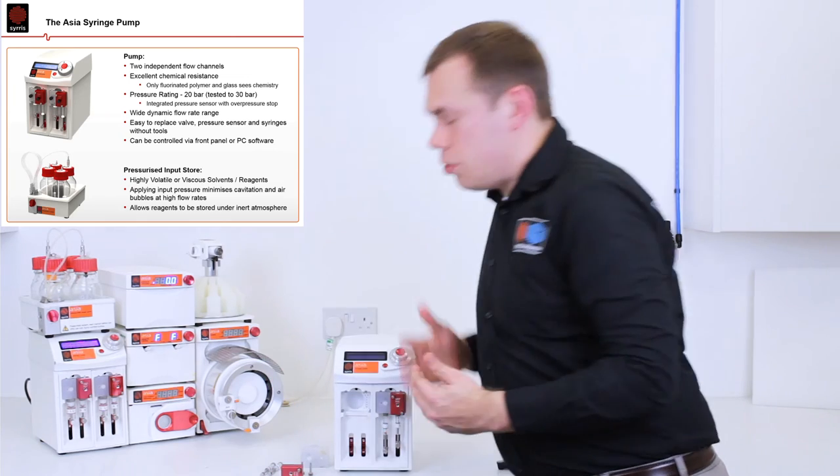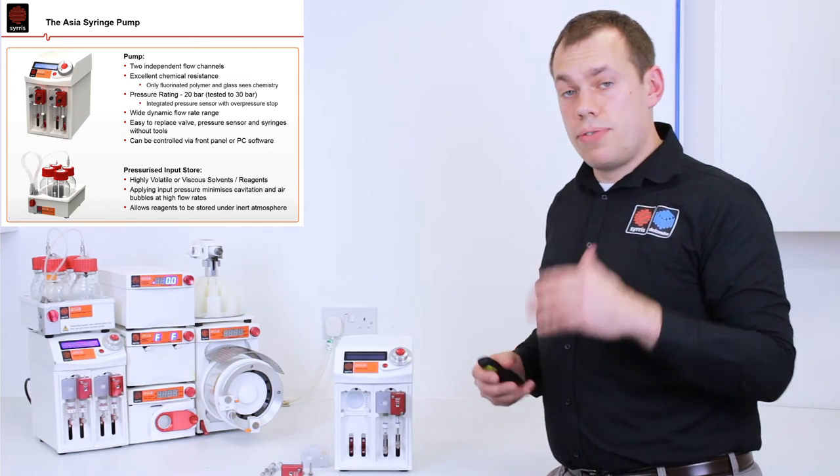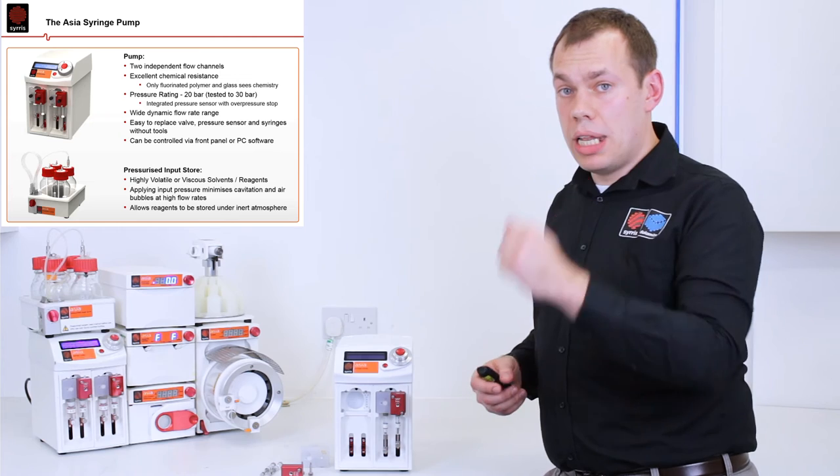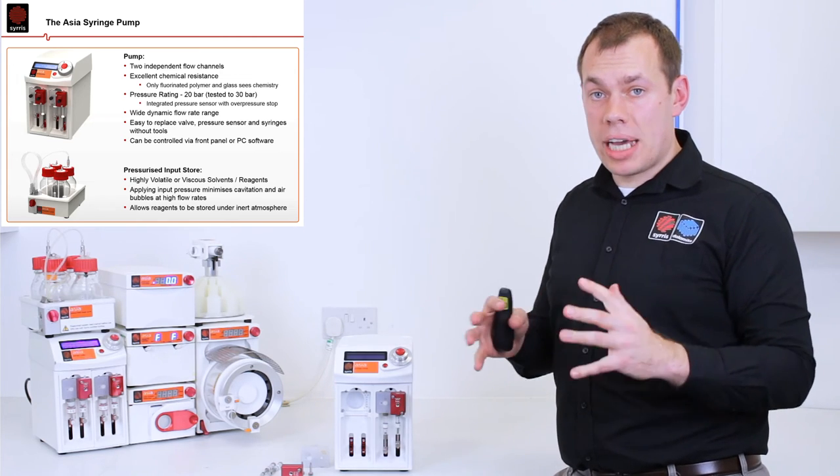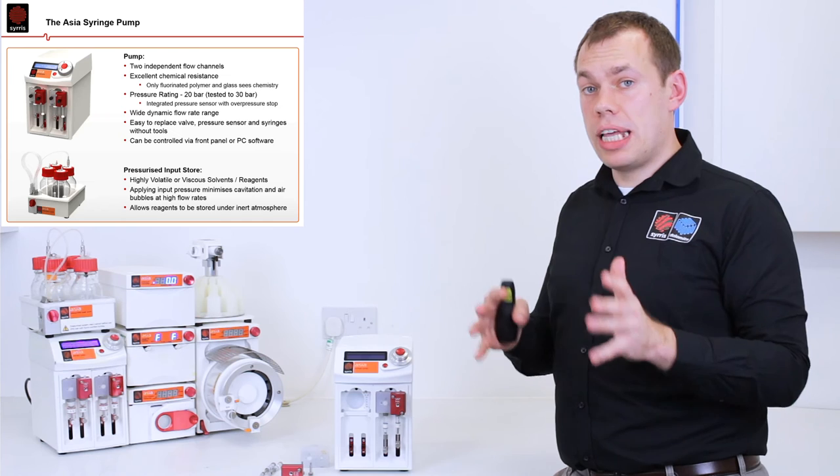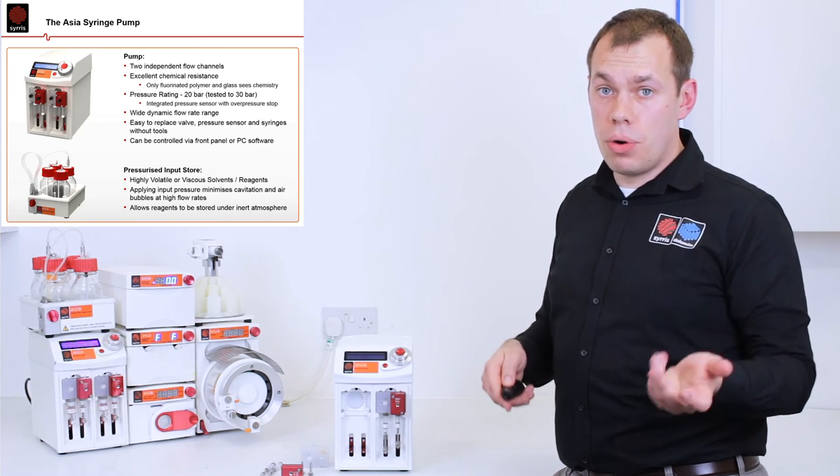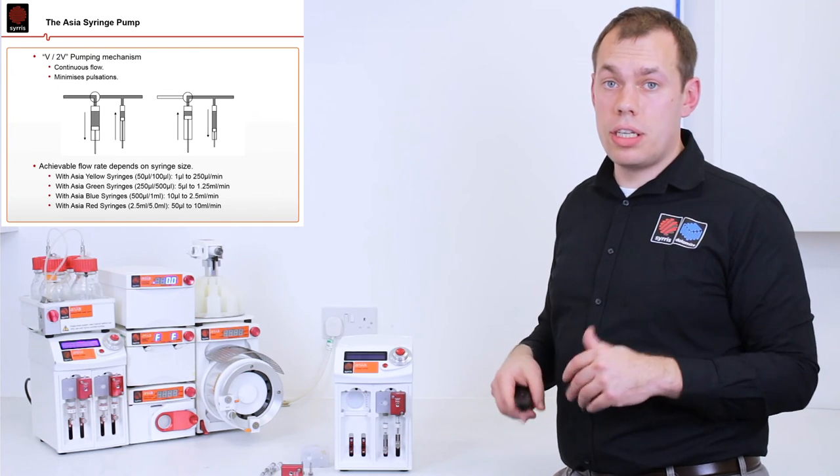The pump allows you to access flow rates from one microlitre per minute up to 10 millilitres per minute. In order to enable maximum precision, you have to select the right syringe size for each flow rate that you want to achieve.